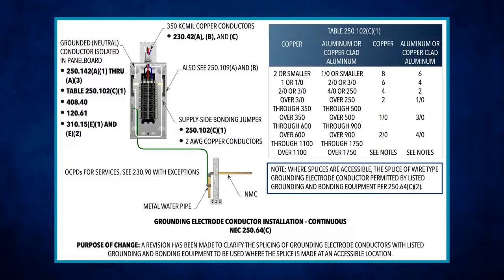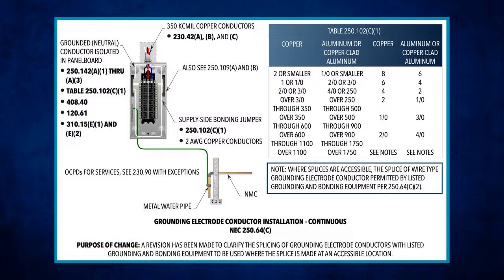And what it says here, grounding electrode conductors and bonding jumpers interconnecting grounding electrodes shall be installed in accordance with one of the following. The grounding electrode conductor shall be sized for the largest grounding electrode conductor required among all electrodes connected to it. True. Okay. 100%. So if you go off your service, you're basically going to tell me that I can put a bar there, termination bar, and come up with number 4, number 2, number 6, but I can feed all that with a number 8 when it's telling you not to here where you're doing interconnection of them.